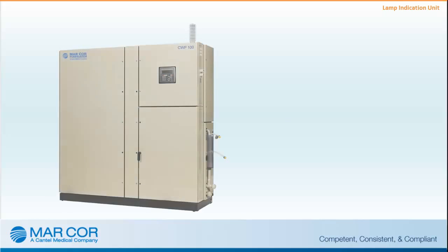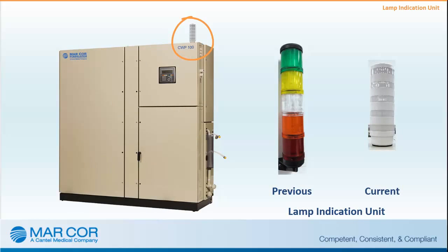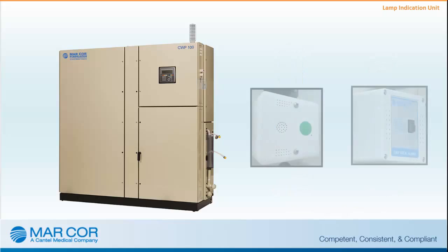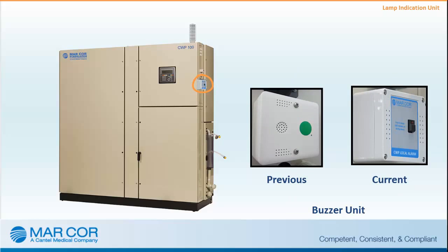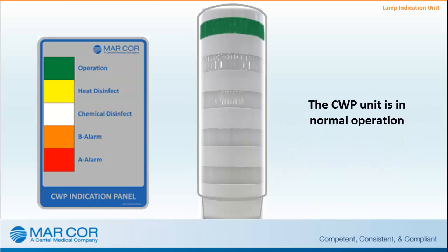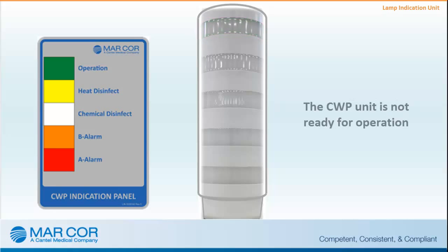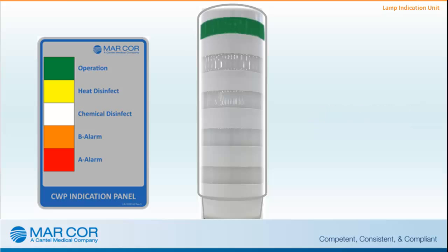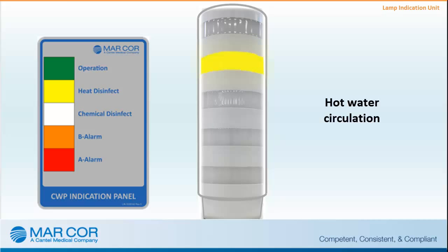The CWP unit is connected to the Lamp Indication Unit and Buzzer Unit. The Lamp Indication Unit gives information about the present state of the CWP unit. A separate additional light is placed in a suitable location with good visibility in the patient treatment area. The buzzer unit issues an audible alarm sound when an alarm occurs, and is silenced by pressing the button on the buzzer unit. A steady green light indicates normal operation. A blinking green light indicates the system is not ready for operation — occurring five minutes prior to startup, five minutes prior to a programmed shutdown, or when the return product water temperature is elevated. A steady yellow light indicates the pump in the heating unit is in operation, circulating hot water in the distribution loop.